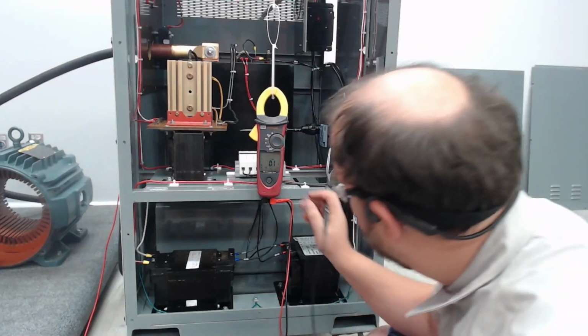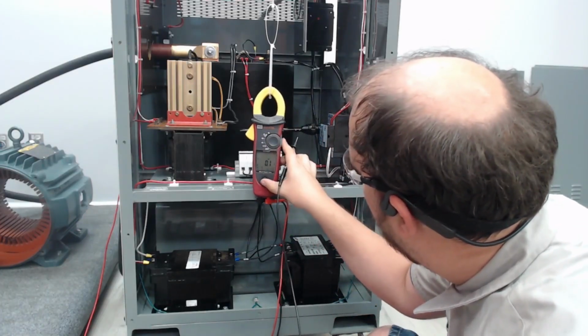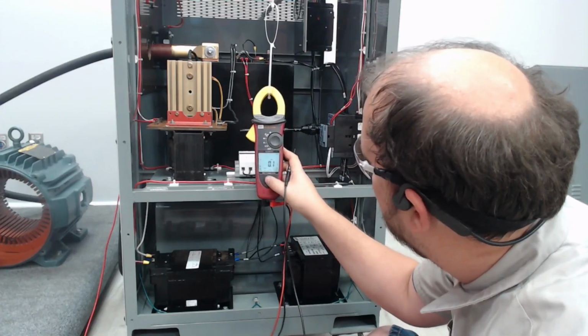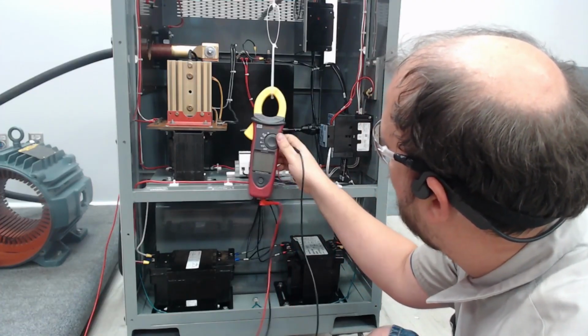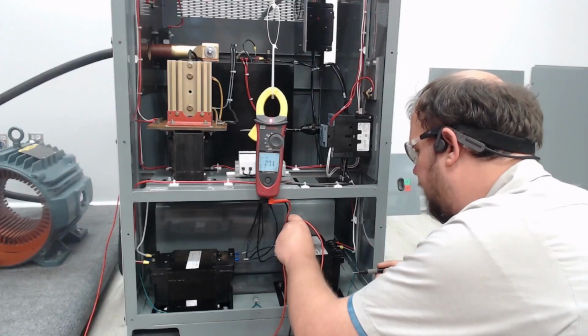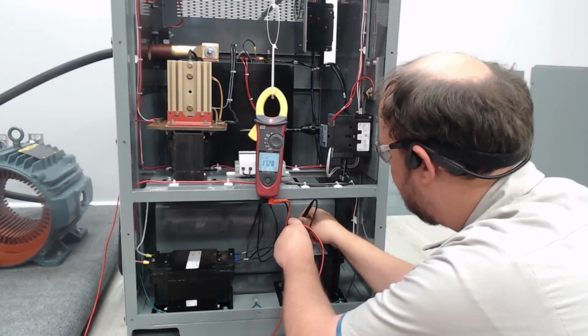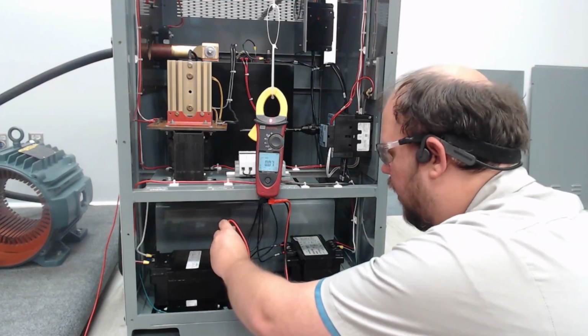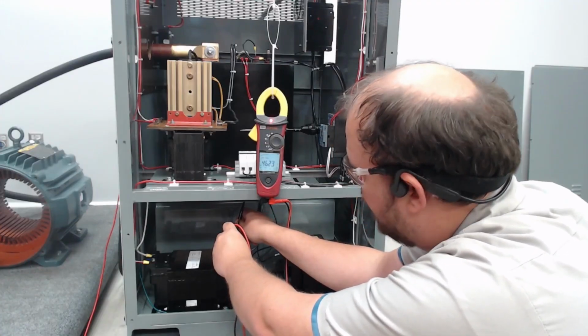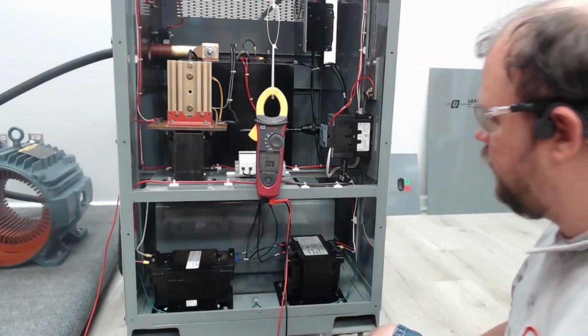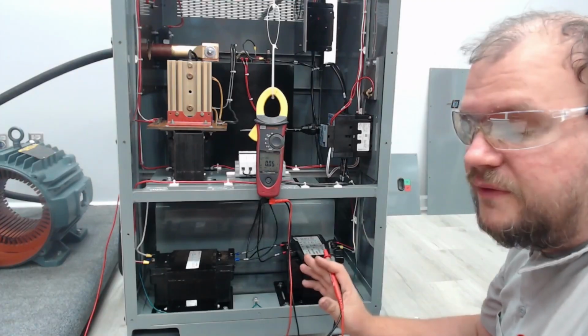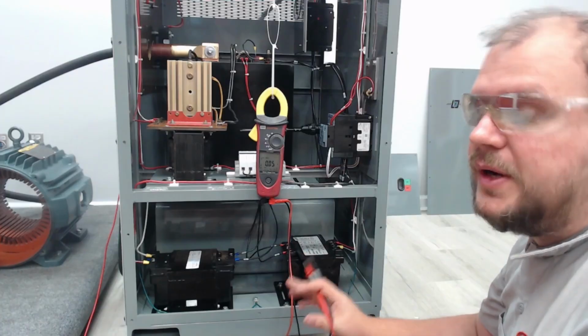Now, you don't need to know any understanding, but you can at least take the initial reading. So volts AC, I don't need min-max anymore, so I'm going to clear that off. And we're going to take a reading of the incoming. This unit is on and operational. So I got 460. I'm going to read the bigger transformer. It should also be reading the same. 460. All right. If you have anything other than 460 or the nominal voltage you should be getting, then you have a problem and you need to rectify that first before you move on.